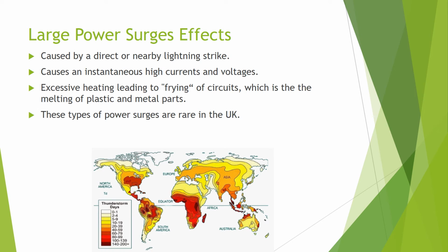The effects of large power surges can be more detrimental. Large power surges are caused by a direct or nearby lightning strike. These surges lead to instantaneous high currents and voltages. The excessive heat caused can lead to frying parts of the circuit. These types of power surge are rare in the UK due to the irregularity of a lightning strike occurring.